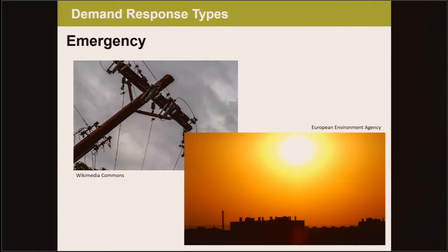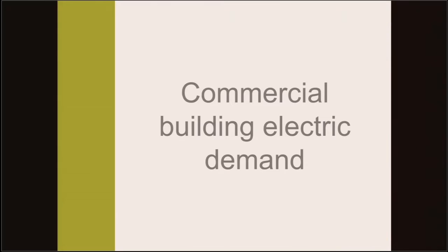A second type of demand response is emergency. It often coincides with the same period as economic examples, such as when it's very hot out. However, it can also be induced by climactic events such as wind, snow, and ice. Building owners and operators agree to reduce their power consumption upon utility requests when the grid is stressed. Recently, smart grid technology has developed to allow utilities to send these signals to customers, often as little as a few hours ahead of time, to reduce their demand for a certain period. Building owners and operators can then choose to reduce their demand in a variety of ways. As an HVAC engineer, I typically think of this as letting temperature set points drift during this period so that the cooling equipment doesn't have to work as hard. But to understand other ways demand can be reduced, we need to understand the ways in which buildings use electricity.